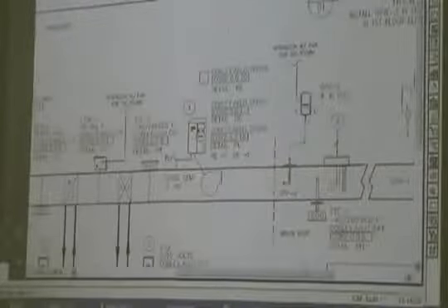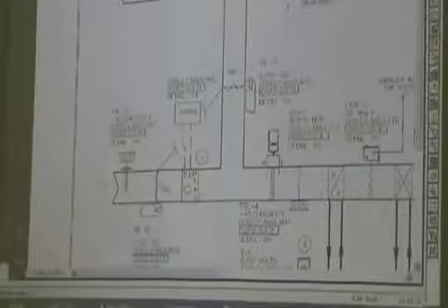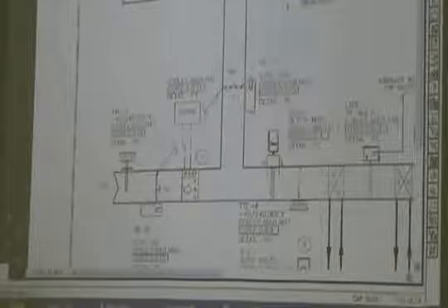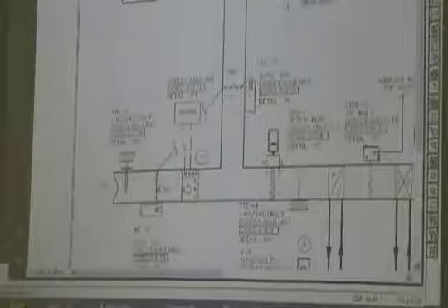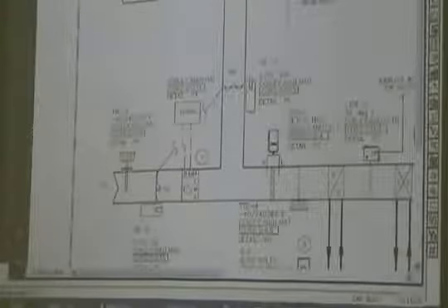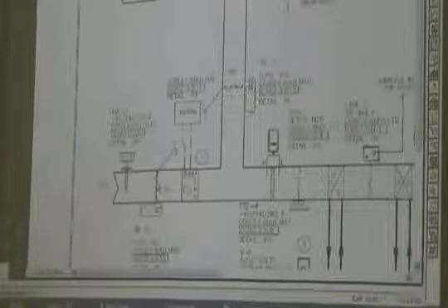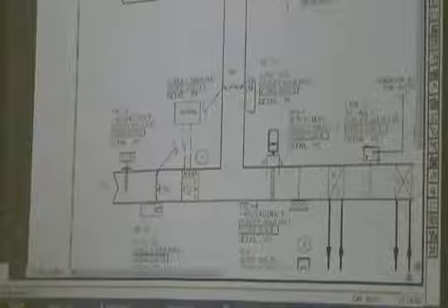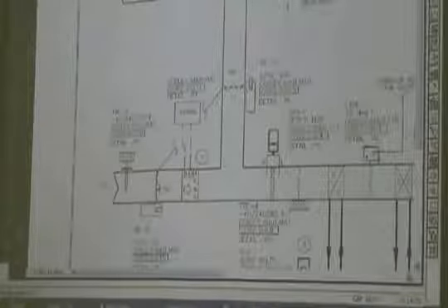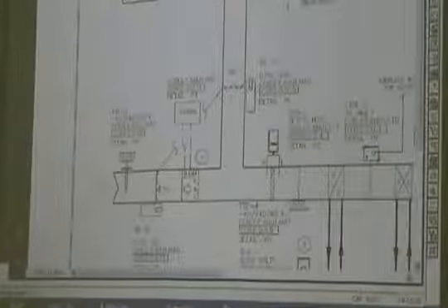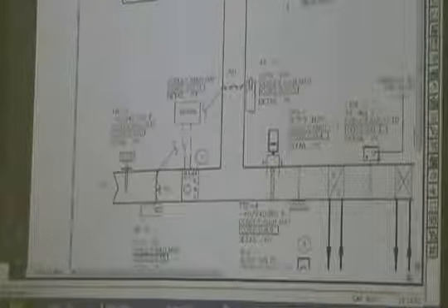Would you take 100% outside air at that time? Think about it. If we say now we're going to use outdoor air, but what are we trying to maintain at the discharge? Down here we're trying to maintain 55. So this becomes our cooling now. So yes, it's going to go wide open. And then I'm going to mess up the building pressure, with a lot of outside air. Right here now, this is going to go closed. This now is going to take on a role of maintaining space pressure. So you're going to start relieving more air. So yes, that's a concern, but you take care of it in another part of the sequence.